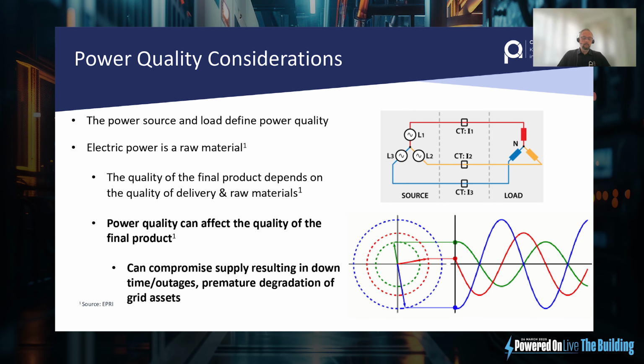Ultimately, why do we care about this? It doesn't matter what you're producing, whether it's electricity to charge an EV, or products like bottled drinks, be it alcohol, fizzy drinks, or food processing. At the end of the day, if the signal coming in to provide power to your equipment isn't healthy, your equipment is going to degrade and fail. Likewise, your equipment may not operate as it should. In the case of an EV charger, if you've got bad power quality coming into it, it's not going to be able to charge the EV properly. And vice versa, if the EV charger is causing problems within the facility, then the transformer is going to have issues, and then all the other EV chargers and other equipment on the system will be affected.